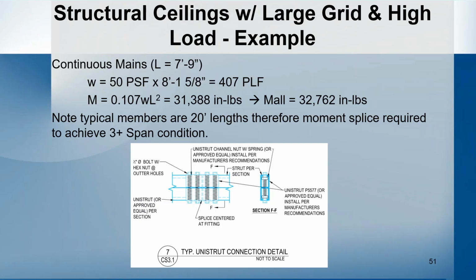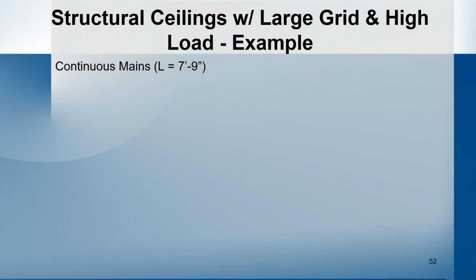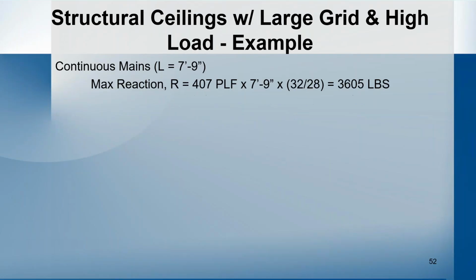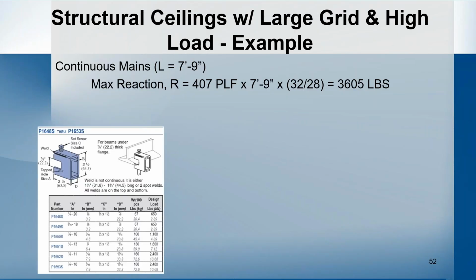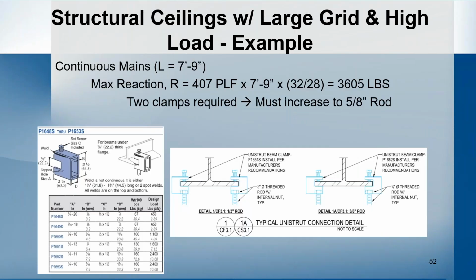And so doing that, for the manufacturers, as long as you're filling the holes and using their splices, then it works as a full moment splice. So then as far as the reactions, we end up with approximately 3,600 pounds. Looking at the table for our clamps, in this case, a 5/8 would be required, but to get 3,600 pounds, we need to use 2 5/8 inch clamps to make this work. None of the single ones have a design load that meets the requirements.